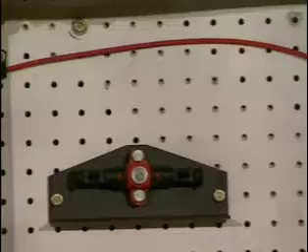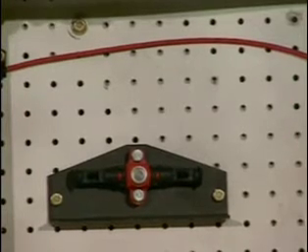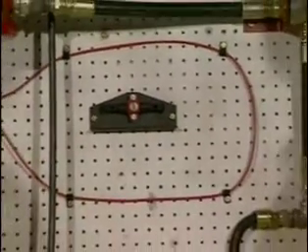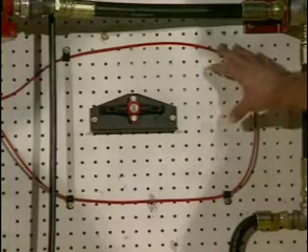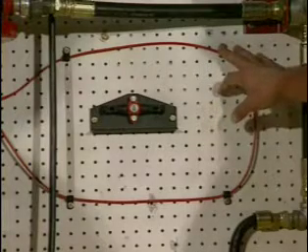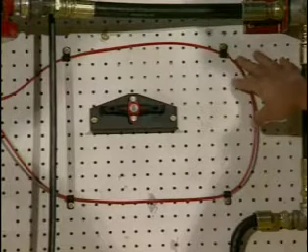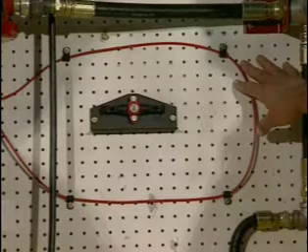This is a thermal detector, which is this device right here in the middle. You're going to have the same problem with this detector as you are with that. If you get a coat of anything on there, it's going to change the rating on that particular unit, whether it's a detector or a detection wire. If you get a coat of mud on it, you're going to change the rating. It's no longer going to be the same rating because of that mud, paint, or anything on those.